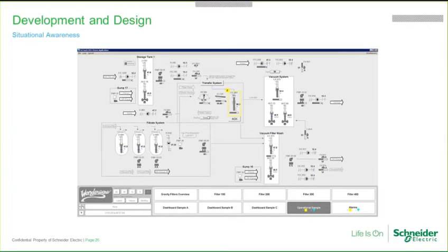principle is that it's the design of diagrams and should be conducted in such a way that it's very easy for an operator to determine between normal operation and non-normal operation. And it should be very easy to distinguish if a signal is in the normal range or near outside the normal range. Our friends at Wonderware have made substantial changes to InTouch to incorporate this in their latest release.